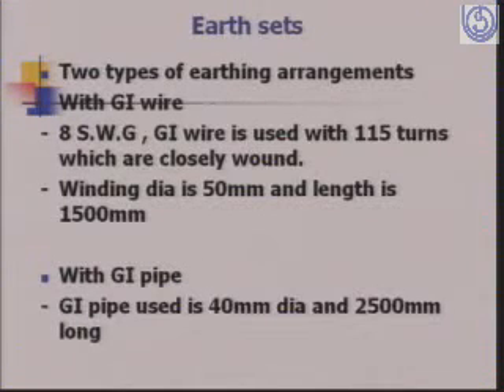Then we have the earth sets. Two types of earthing arrangements with GI wires are used. 8 SWG GI wire is used with 115 turns, which are closely wound, and the winding dia is 50 mm and length is 1500 mm. Or we could also have it with GI pipe. GI pipe is used as 40 mm dia and 2500 mm long. These are used for earthing the poles.